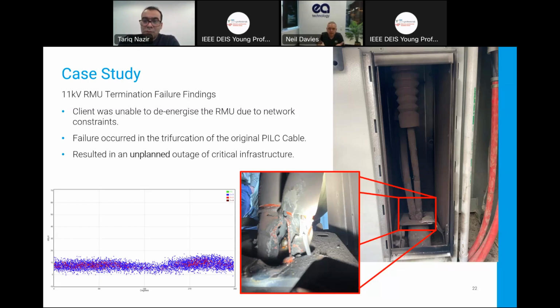You can easily do this, in all honesty. If you've got partial discharge in the field and you can't grab a true 50 hertz reference, then you can usually tune the instrument by going into a manual mode and seeing which way the clusters drift, left to right, and adjust the frequency to get the clustering to be steady. So what you're typically looking for on any PRPD is two clusters of activity 180 degrees apart with a stochastic type, so slightly random around that same point of 180 degrees apart. So, stochastic nature on the PRPD. You can interpret a lot from the PRPD plots nowadays.